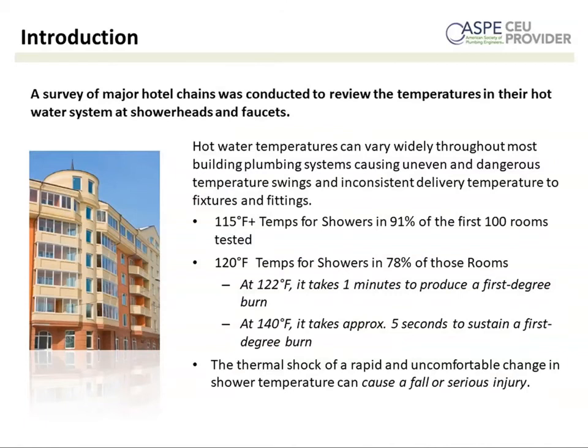Recently, a study was done of major hotel chains, just as some real life information, where over 100 hotels were sampled for their hot water temperature in guest rooms. In 91% of the first 100 rooms that were tested, we found temperatures of 115 degrees Fahrenheit and greater. And in 78% of those rooms, we found temperatures of 120 degrees Fahrenheit and greater. And again, just to remind everyone, at 122, it takes about a minute to produce a first-degree burn, and at 140, minutes become seconds.